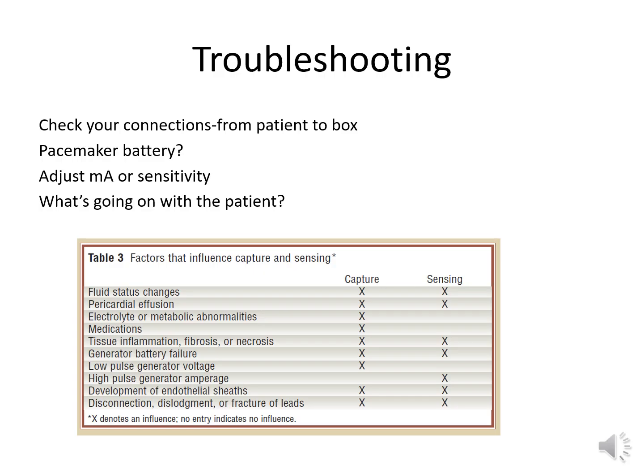Okay, troubleshooting the pacemaker. Your pacemaker is not working right. So start with looking at the connections. Start from the patient and work your way to the box. Make sure all your connections are tight. Check your pacemaker battery. Do you have enough battery power? If it's an issue with the box, replace the box. Do you need to adjust your mA or sensitivity? We just went over that.